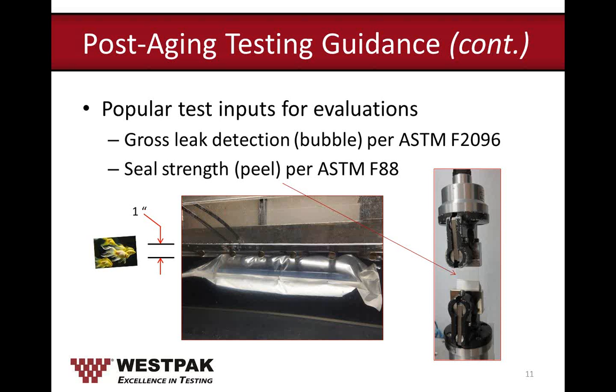The second popular test is seal strength, also known as peel — used to determine how much force it takes to open the package. There's no universal acceptance criteria for this; it should be determined by you through seal validation: IQ, OQ, and PQ. A very common starting point is the one pound per inch requirement. There are three testing techniques for peel testing: the unsupported technique, which is the most conservative; the supported 180-degree technique; and the supported 90-degree by-hand technique. The two most popular among our customers are the unsupported and supported techniques — in 12 years here at WestPak, I've only performed the supported 90-degree by-hand technique three times.